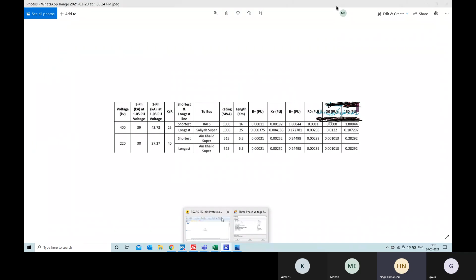I have a question for you. Whether it should be 400, or 400 into 5 percentage, 420. What value should I give there? Whether it is 400 or 400 into 5 percentage of that. I should give 400, because the 420 will happen only after the fault, right? Yes, exactly. So the system voltage will not change.